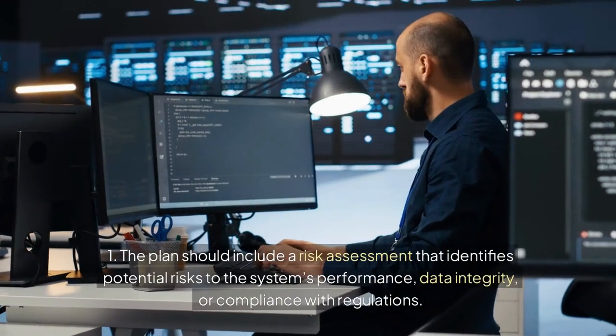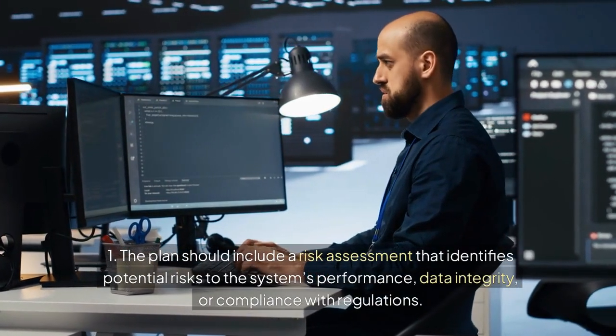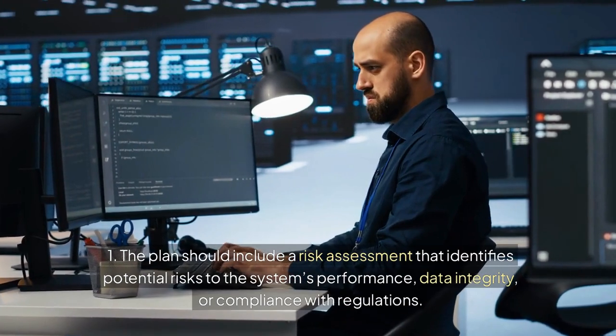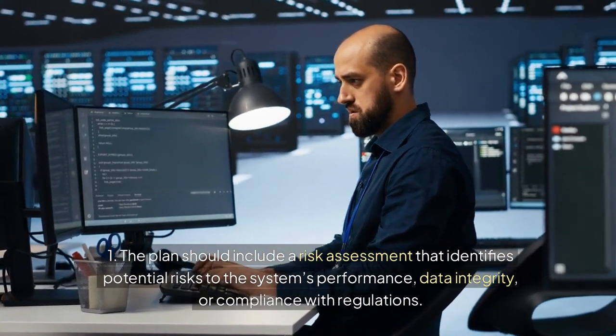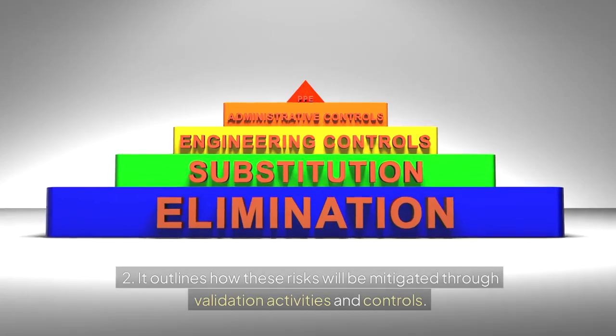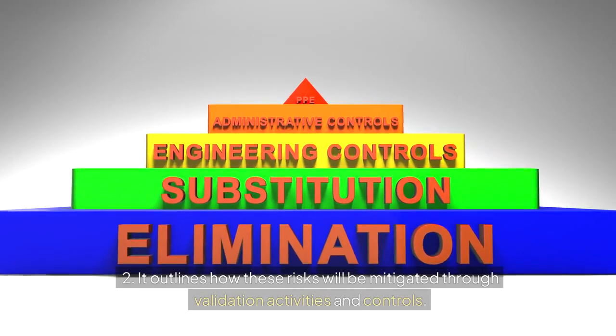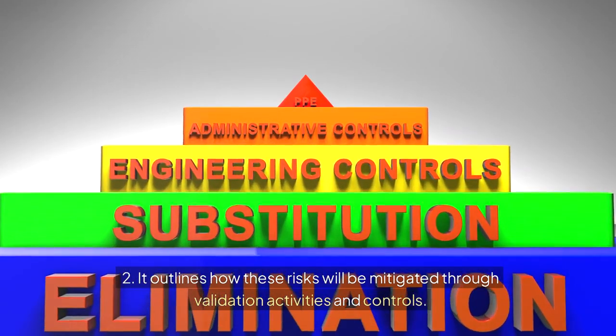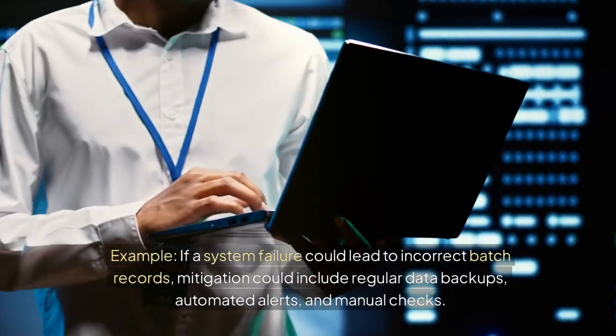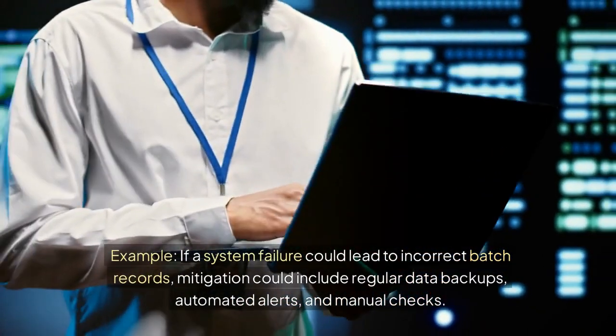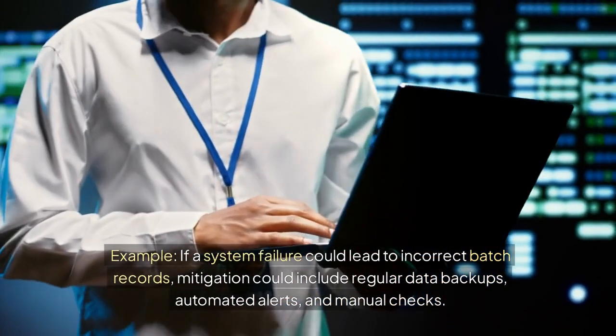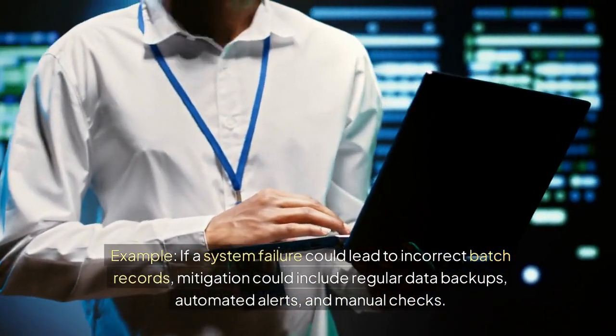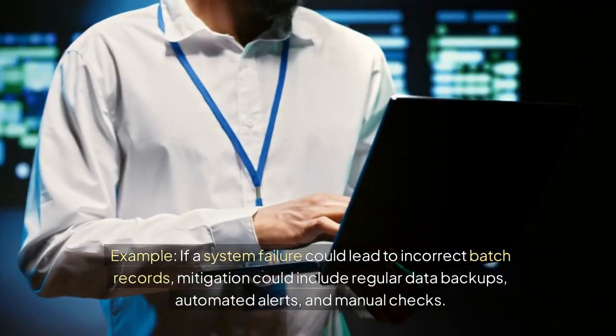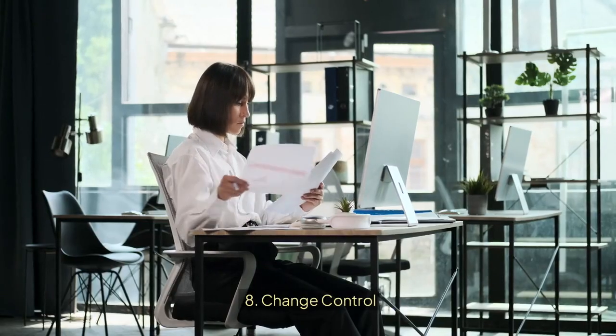7. Risk management. 1. The plan should include a risk assessment that identifies potential risks to the system's performance, data integrity, or compliance with regulations. 2. It outlines how these risks will be mitigated through validation activities and controls. Example: if a system failure could lead to incorrect batch records, mitigation could include regular data backups, automated alerts, and manual checks.